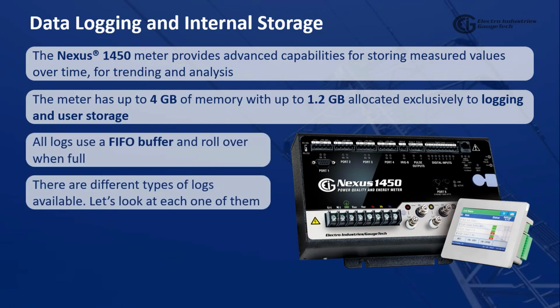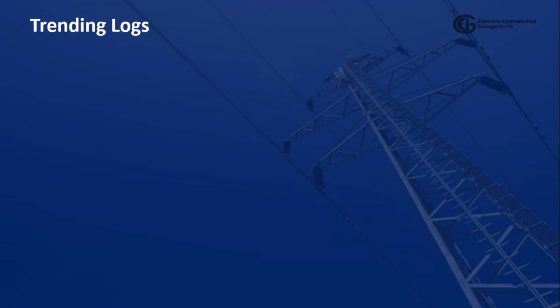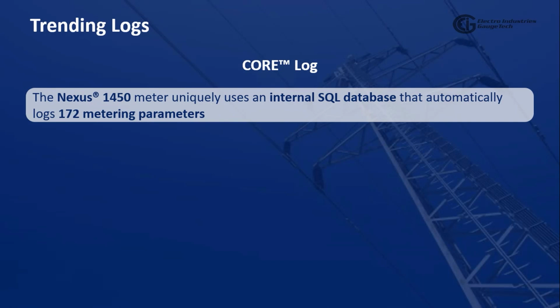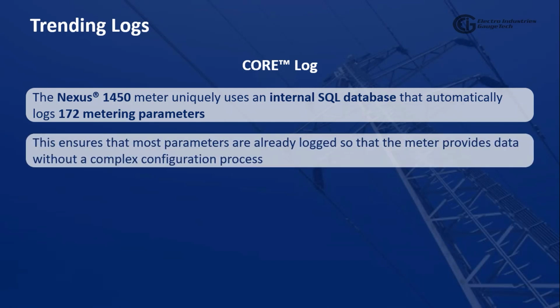There are different types of logs available. Let's look at each one of them. The first one is trending logs. This further includes core log. In this, the meter uniquely uses an internal SQL database that automatically logs 172 metering parameters. This ensures that most parameters are already logged so that the meter provides data without a complex configuration process.